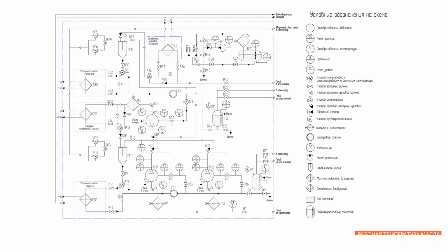The optimal oil operating temperature for long-term machine use is between 92-98 degrees Celsius. Under these conditions, the standard alert setting for helium temperature at the end of the compression process is 105 degrees Celsius. The emergency threshold is 110 degrees Celsius.